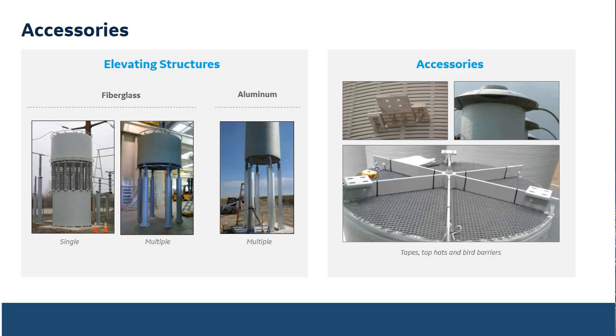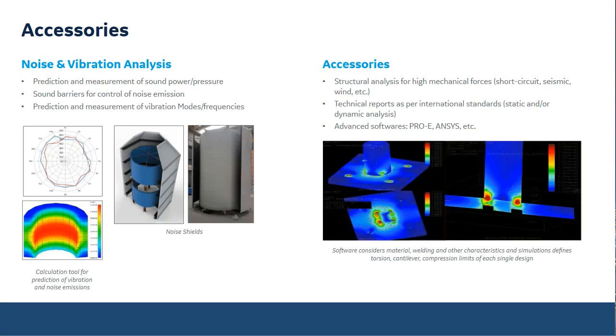Some reactors can be provided with taps, inductance taps, like a minus plus 2% inductance tap, for example, filter reactors. They can be provided with top hats to limit the flow of snow or pollution accumulation on top of it, although the reactors are prepared to withstand the environmental conditions. This is just a way to enhance the duration throughout the 30 years that I mentioned before. They can also be provided with bird protection, because the reactors are going to run at a higher temperature than the ambient, especially in wintertime. That's a very cozy place for birds and animals to be in. So we could provide bird barrier protection so animals cannot get inside of the coil. So this is just for information as well.